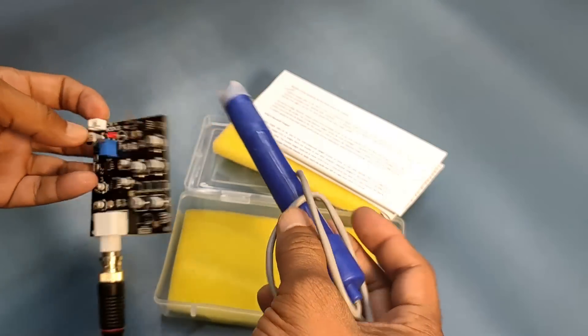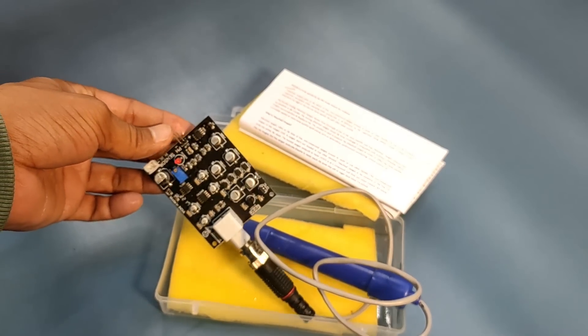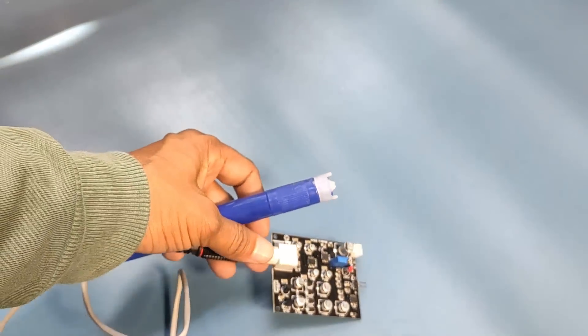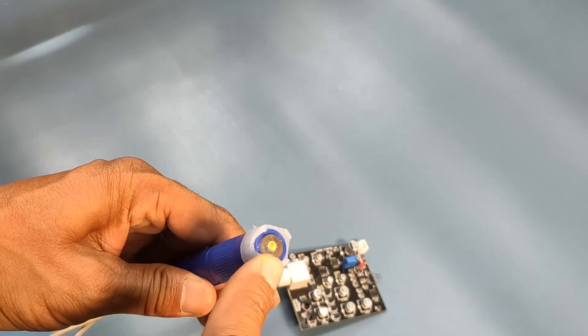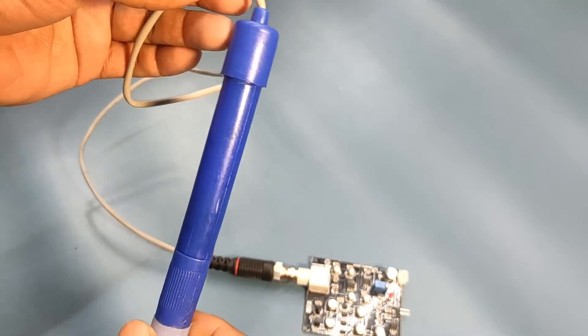The oxygen permeable membrane in the membrane cap is sensitive and fragile. Use caution when handling it. Note, fingernails and other sharp objects should be avoided in order to protect the D.O. membrane from getting damaged.